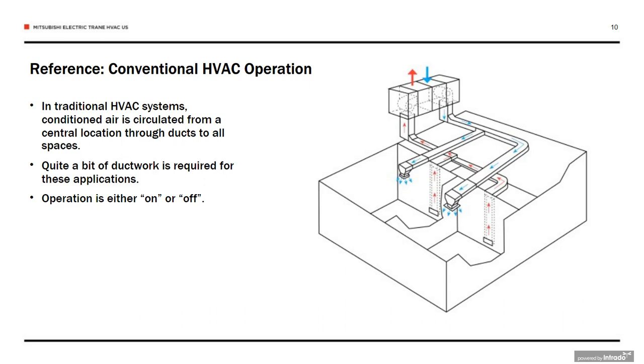In contrast to the VRF system, conventional systems like the one shown here, a rooftop unit with a single zone, is connected to the space with ductwork. This ductwork, again, is connected to that rooftop unit to deliver the heating and cooling necessary for that building. Now, with this application, there's typically large ductwork, and you're going to have to balance the system to make sure that the comfort level is where you want it to be. Again, we've been doing that quite a while here in the States, and it requires a lot of energy to move that air, as well as the different components that are required to control the system to deliver the comfort that you need. A good example of some of the comfort problems that this creates is in a commercial office where you have 3 or 4 offices sharing one unit that is controlled by one thermostat.